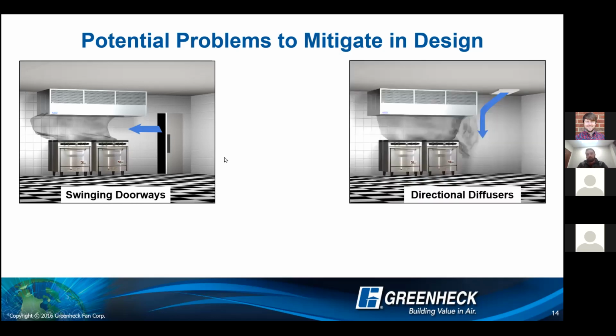The next one, and probably the most controllable one by the engineering community in my opinion, is the placement of diffusers and the use of directional diffusers in a kitchen. I would say that we would recommend never using a directional diffuser within a kitchen space. It just has the potential for that air to be shot back towards the hood and disrupt capture. And then ideally, you won't have any diffusers, whether they be perf or directional, within 10 feet of the hood.